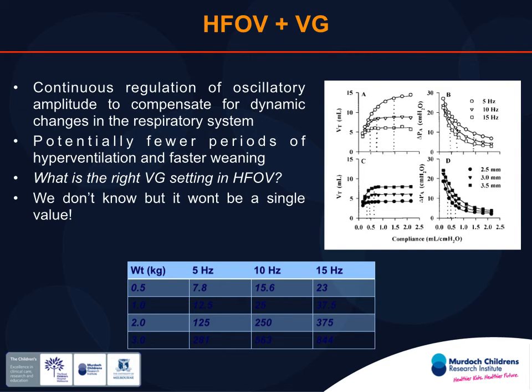Okay, and it's a bit like on conventional. The volume guarantee you set on the ventilator is only as important as the role of volume, the tidal volume and the rate, because the rate is also important. It's the CO2 clearance we're interested in. These numbers are big changes. So if we change our frequency, unlike on a conventional ventilator, we will have a big effect on the volume guarantee settings. So if we're going to use this mode, again, it comes back to understanding frequency.